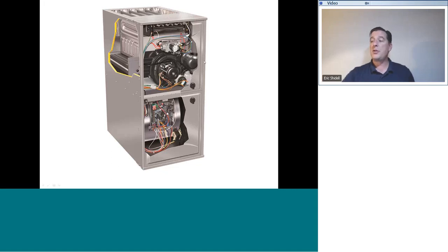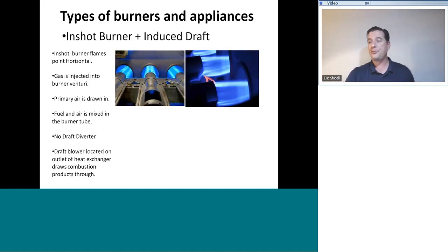The draft inducer does push through the flue on the 90% furnace, and that flue is going to be a plastic PVC pipe that can either go vertically or horizontally because of that pushing effect. Here's another look at the way those burners move their flame sideways. Once again, here is that Venturi.